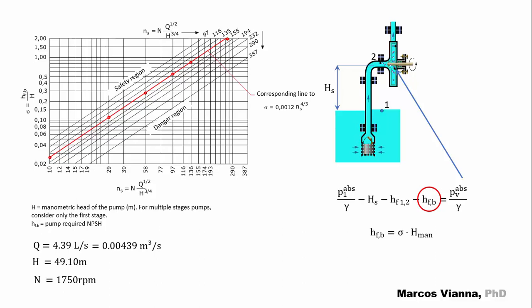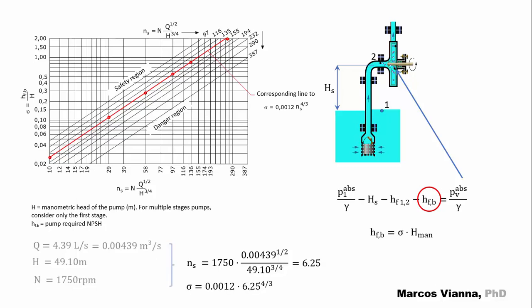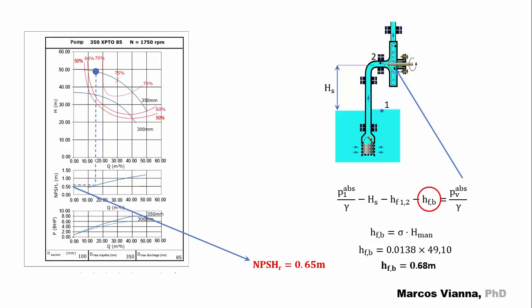Here are the values that we found in our last video. The corresponding specific speed can be calculated — here it is. The same can be done for the cavitation coefficient — here is its value. Now we can calculate the value of HFB, and this is what we find. It's not very different from the value that we found for the required NPSH in the pump chart, but for practical applications it's usually well above it.